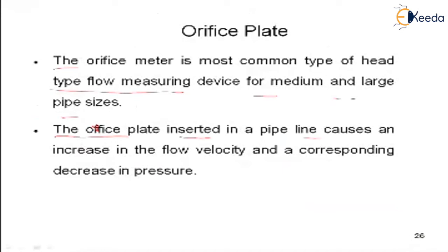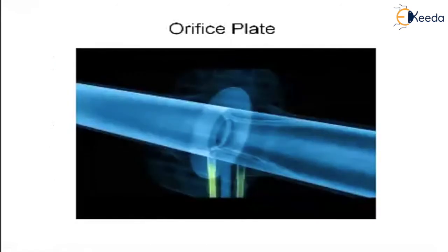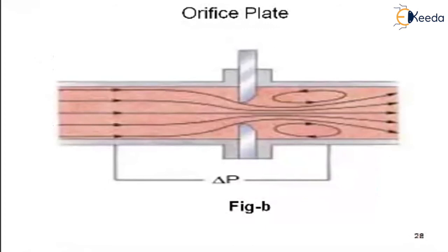The orifice plate is inserted in a pipe and causes an increase in flow velocity with a corresponding decrease in pressure. Here the velocity is increasing at the orifice, while the pressure is decreasing. The pressure before the orifice is P1, and after is P2. The difference P1 minus P2 is the differential pressure. The liquid flows in and passes through this throat section.